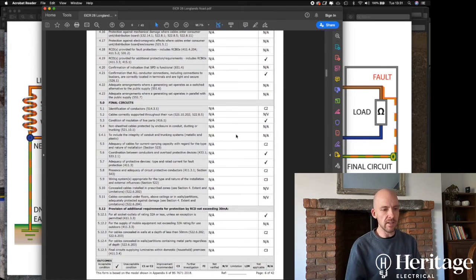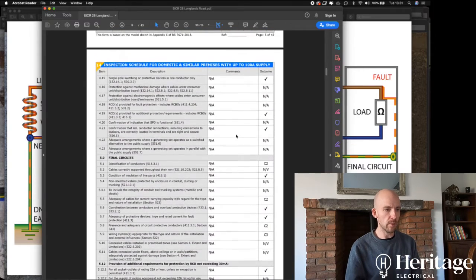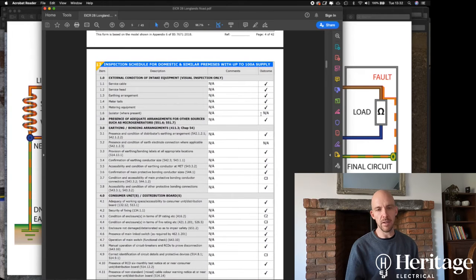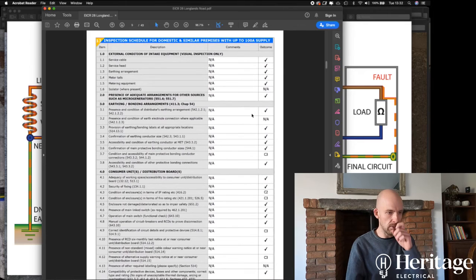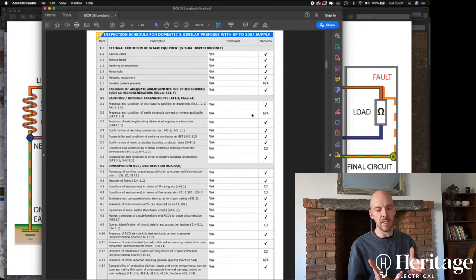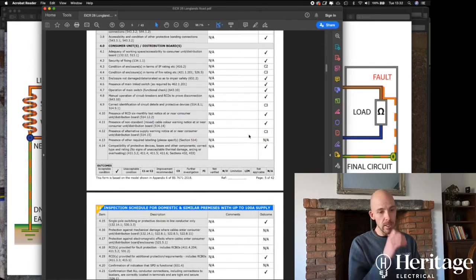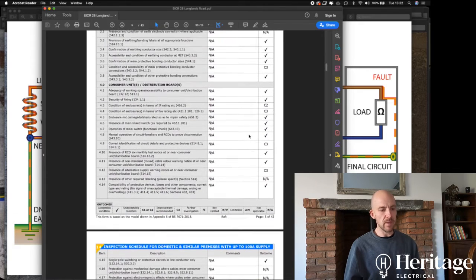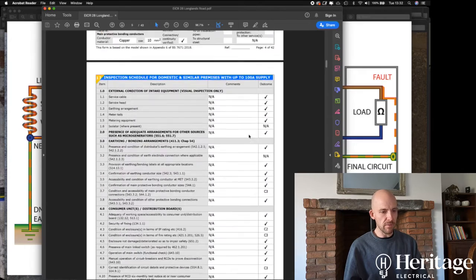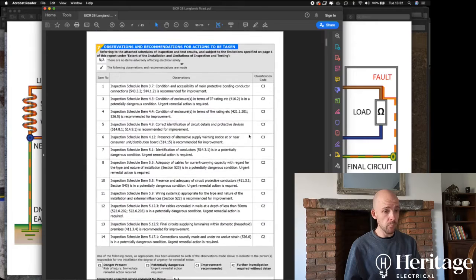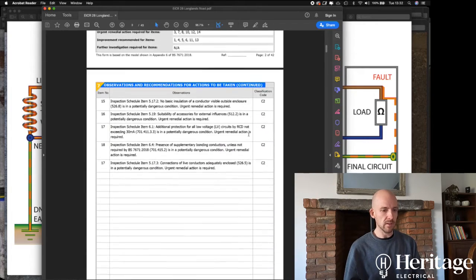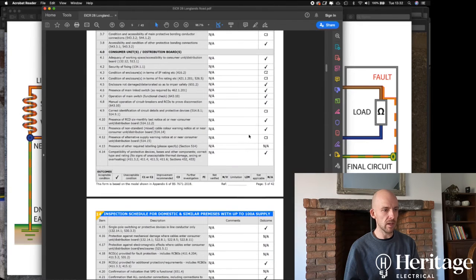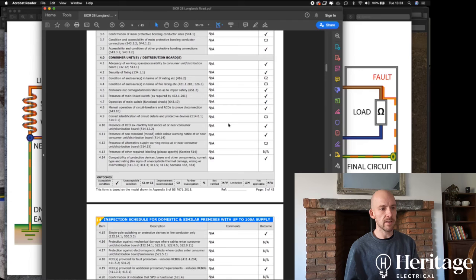So you can see that in this case there's a lot of ticks. There's some that are not applicable, so there was no isolator at the origin where the supply comes into the building, so not applicable, that one. There's no earth electrode in this instance because we're using the main earth that the network operator has provided. And anywhere where you see a tick, that's all good. Anywhere where there's a C2, C3 or a further investigation will get pulled through on the software to this summary of observations which we talked about before. So it's duplicate information. You see we've got the C3 code there, correct identification of circuit details. There wasn't any, so that needs to be provided and upgraded. That is then pulled through here. Yeah, correct identification of circuit details. So that's just duplicate information.